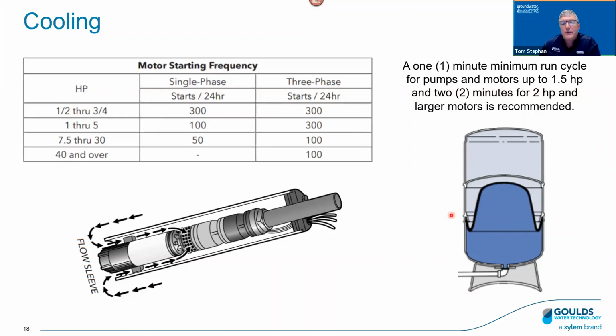And basically it's saying that if you match the drawdown of the tank to the capacity of the pump, then let's say a 10 gallon per minute drawdown to a 10 gallon per minute pump that's pumping 10 gallons per minute, then we have our 1 minute runtime. So certainly the tank size has a lot to do with the proper cooling of our submersible motor.